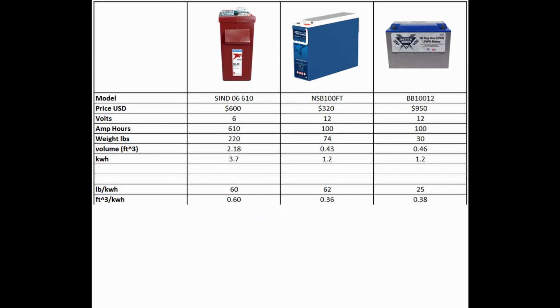The flooded Trojan battery is 0.6 cubic feet per kilowatt hour. The Northstar AGM battery is 0.36 cubic feet per kilowatt hour. And the Battleborn lithium battery is 0.38 cubic feet per kilowatt hour. Note that while lithium batteries weigh less than lead acid, they actually don't take up that much less space. This is due to their less dense materials and the cylindrical cell nature, which waste a lot of space.